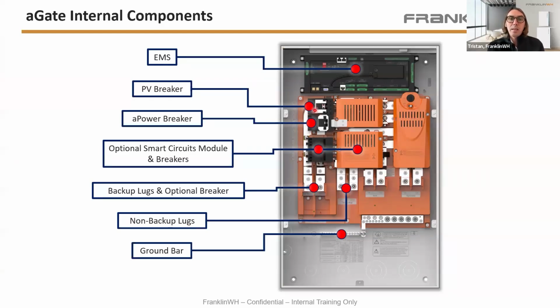One thing to note is that these do accept quad breakers. So when you're doing 2 aPower X's for the battery, you can actually land them on a quad 30. The same thing goes for the PV breaker. If you have 2 7.6 or smaller inverters, you could use a quad 40 for that one as well. And those accept Siemens, Square D, Eaton, kind of the basic breakers that are accessible on the market. The PV input's rated for 80 amps and the aPower input's rated for 100 amps.